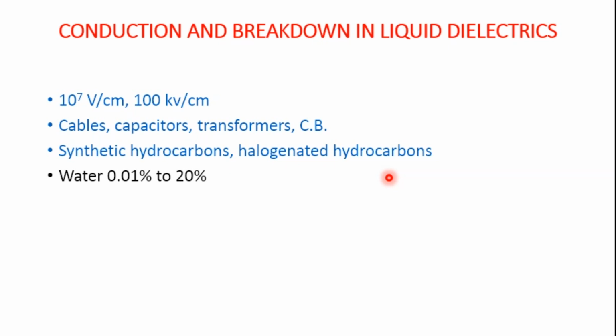Liquid dielectrics are normally mixtures of hydrocarbons and are weakly polarized. When used for electrical isolation, they should be free from moisture, products of oxidation and other contamination. If there is a presence of only 0.01 percent water content in dry transformer oil, the dielectric strength will reduce by 20 percent. So utmost care has to be taken in the case of capacitors, cables, as well as transformer oils.